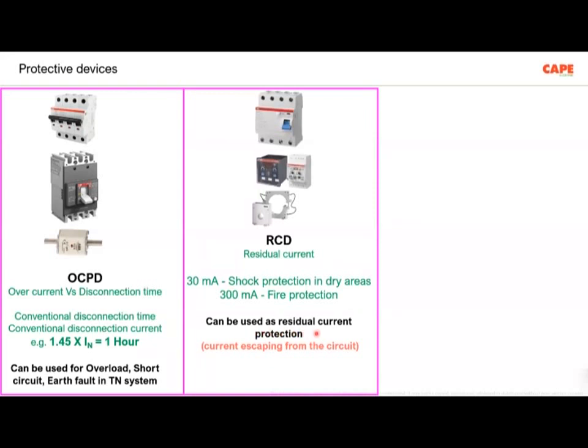So these devices can be used as a residual current device. For non-electrical engineers, I have put it in a tricky way: current escaping from the circuit. Residual current is the current which is not flowing through the circuit. It is actually escaping from the circuit due to some insulation failure or leakage. So if the current escaping from the circuit is more than 30 milliampere, your RCD trips. These devices can be used only for earth fault protection, not for overload and short circuit protection.